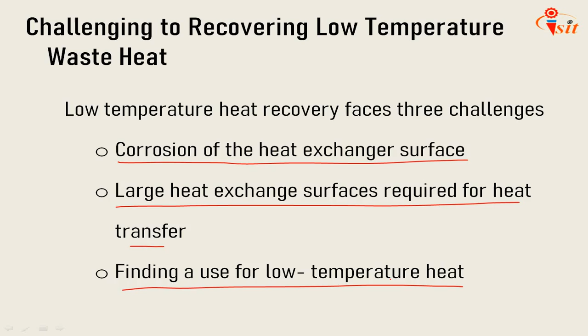Recovering heat in the low temperature range will only make sense if the plant has a use for low temperature heat. Potential end uses include domestic hot water, space heating, and low temperature process heating. Other options include using a heat pump to upgrade heat to a higher temperature to serve a load requiring higher temperatures. Additionally, low temperature power generation technologies are slowly emerging. So these are the challenges to recover the low temperature waste heat.